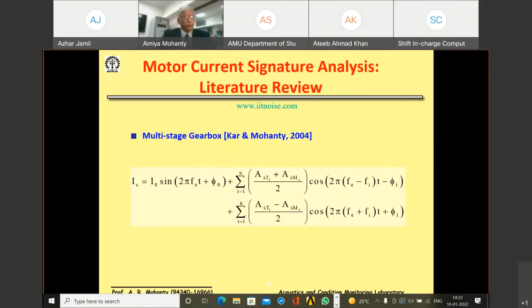Again, in the current signal, we could see all these things: left hand and right hand sidebands of second GMF across line frequency. So that means the motor current signature analysis was established, that this is non-intrusive. It is possible to detect and diagnose the fault as early as possible. The current gets modulated, so we developed algorithms to demodulate the signal and find out the defect frequency. So now you see the power of this technique.